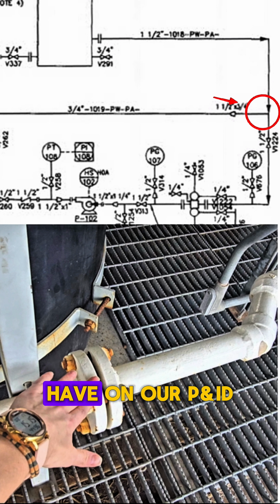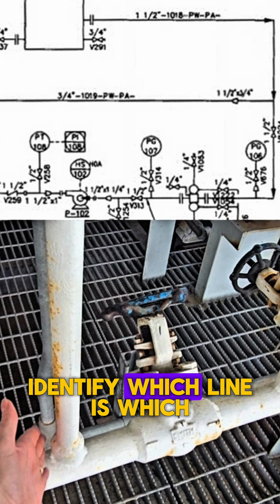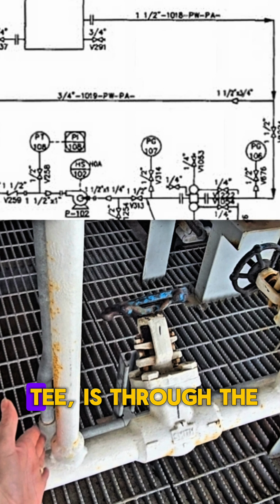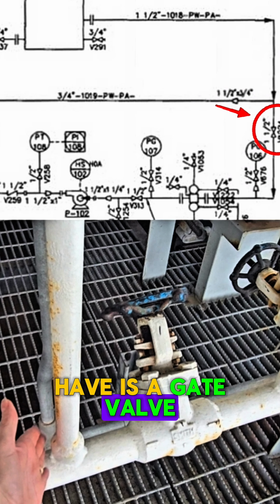The next thing we have on our P&ID is a T. If we follow our piping out, the next thing we have is a T. When you have a T, one of the ways to be able to identify which line is which coming off of that T is through the pipe diameter. If you look on your P&ID, you can see your line number, and the beginning of it says 3/4 inch. So that lets you know it's a 3/4 inch line. If you look at the other part of the T going down on the P&ID, you see 1.5 inches. In this video, we're just walking out the main flow of our P&ID, so we're going to continue with the 1.5 inch line. On our P&ID, the next thing we have is a gate valve.